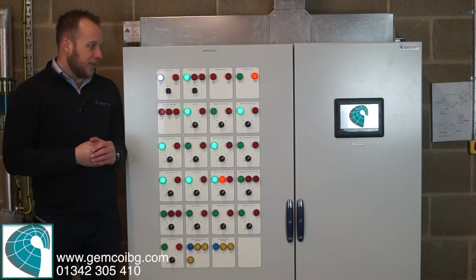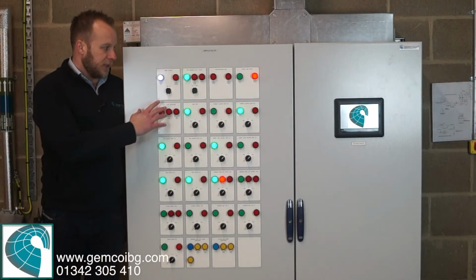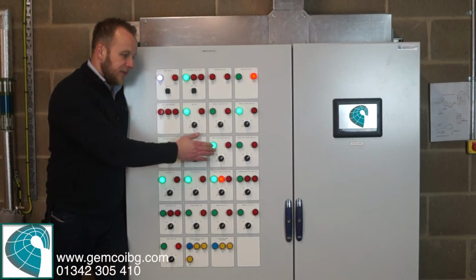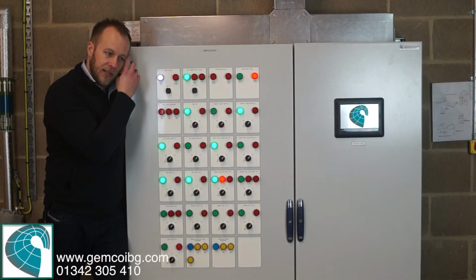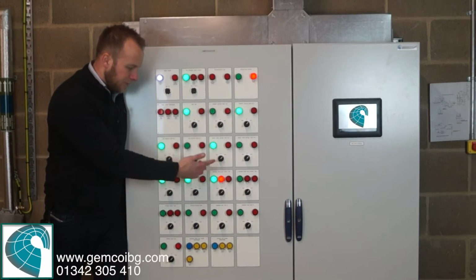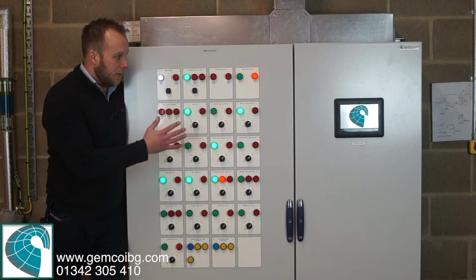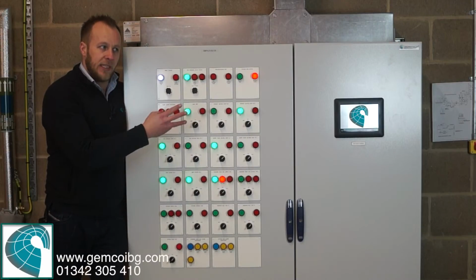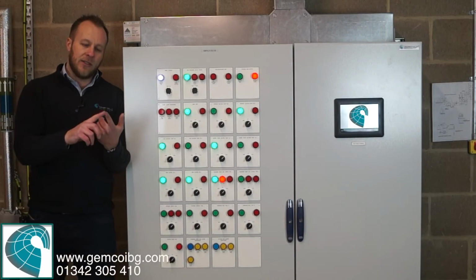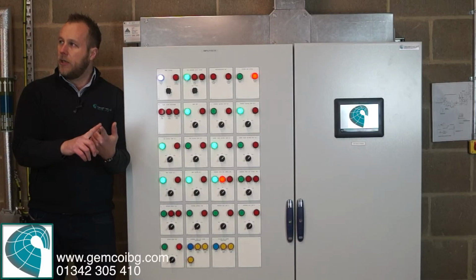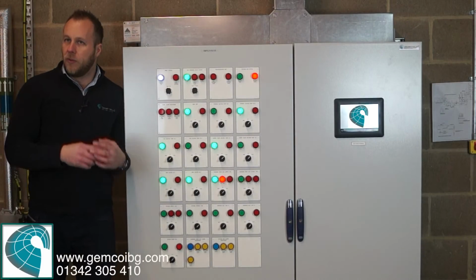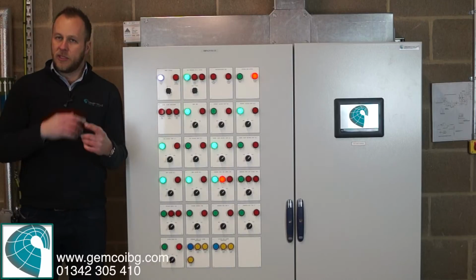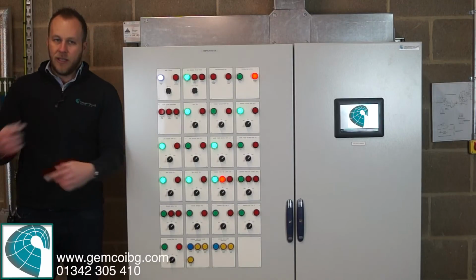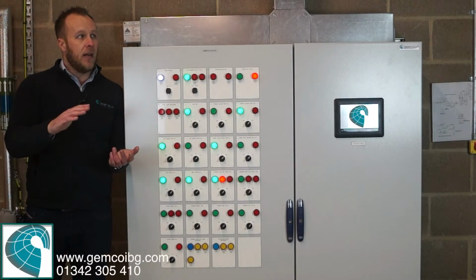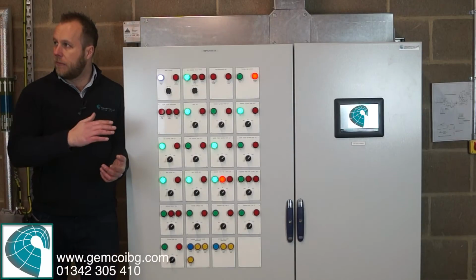Frost protection, other stages of frost protection. If you were to come in out of hours and you've set the time switch off and you think, well, plant shouldn't be running, and you see some pumps running, what that means is it might be under frost protection. We've got 3 stages of frost protection. One is the outside air. If the outside air goes below 0, we just run some pumps, because what we don't want to do is freeze any pipework. So we just start circulating the water until it goes above, I think it's 2 degrees outside, and then we'll shut the pumps off.